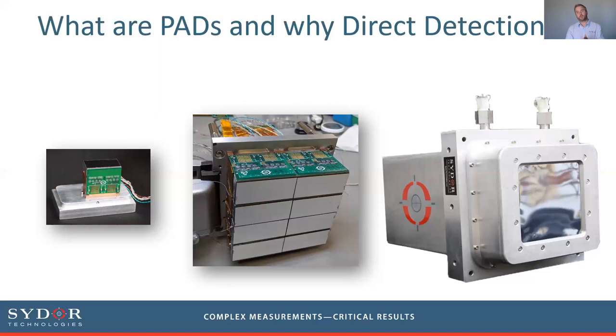In direct detection, the substrate at the front of the device — such as silicon or cadmium telluride — directly converts the incoming x-rays into charge, which is then read out.